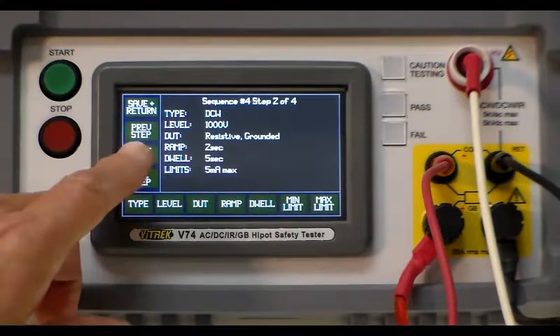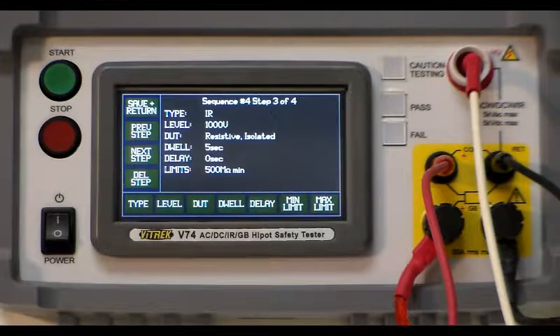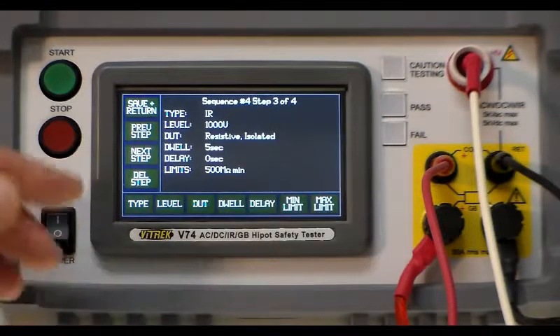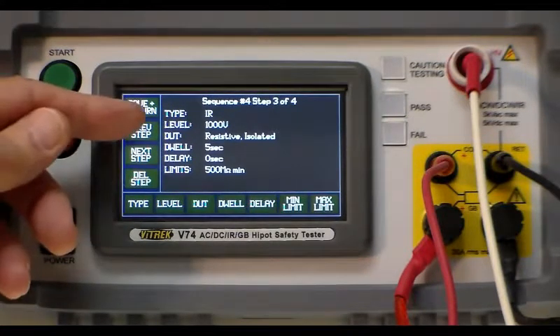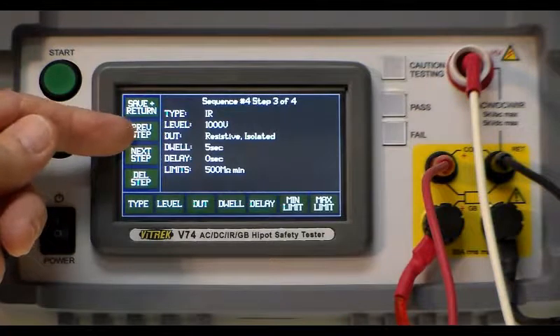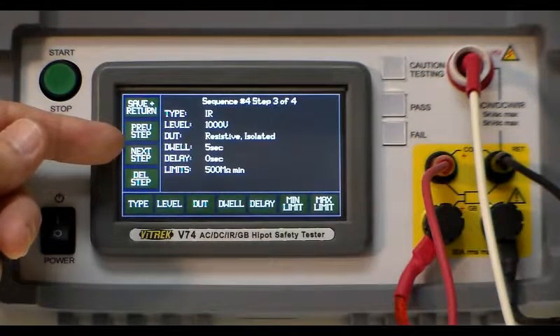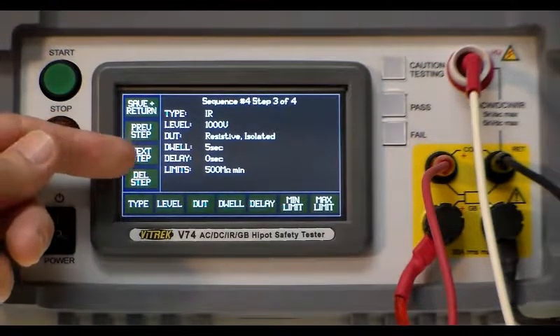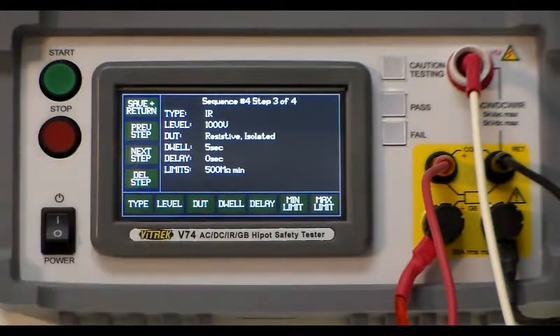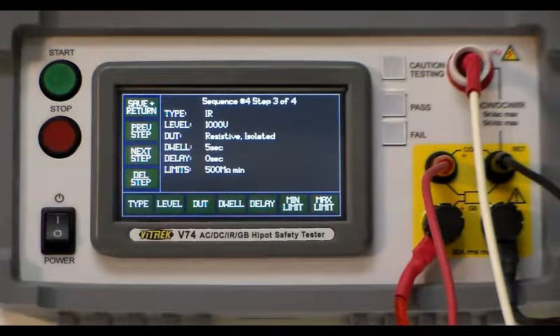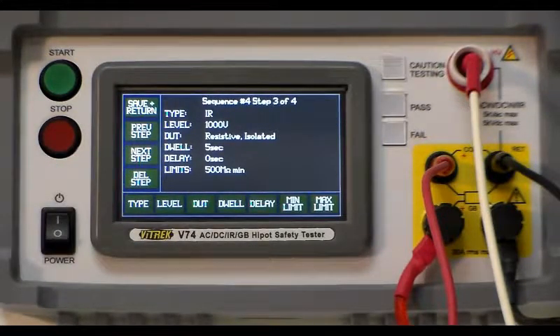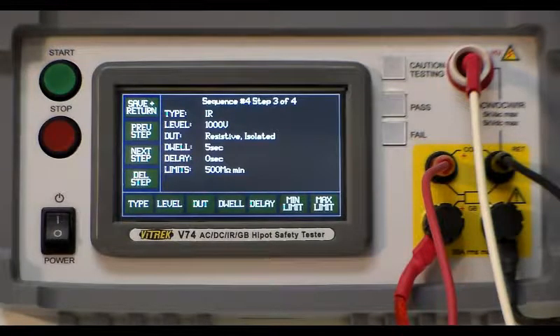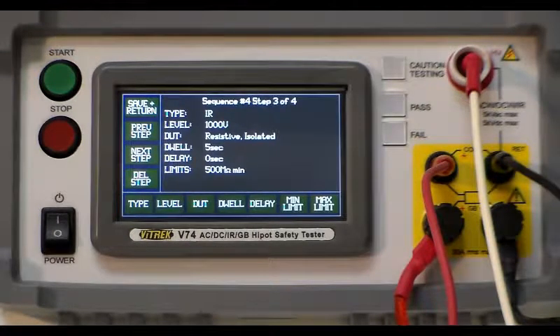The next step would be the IR which is again DCIR. We have it set for a thousand volts, resistive isolated and the dwell time would be five seconds in this case with a delay time of zero. The delay time would be the amount of time that you let it settle before it actually starts enforcing the readings that you're putting in there.